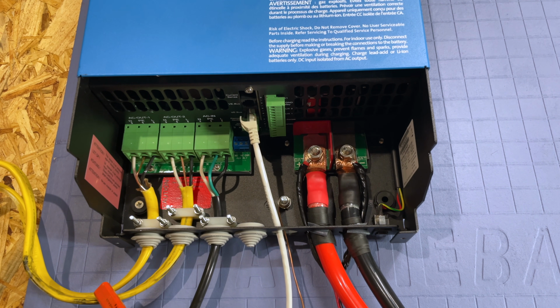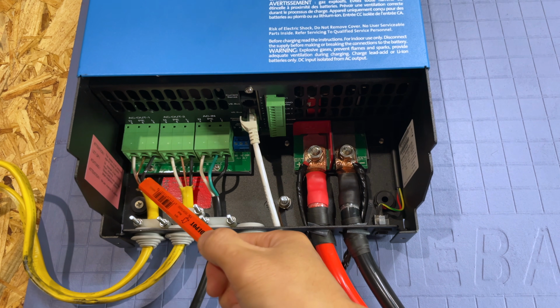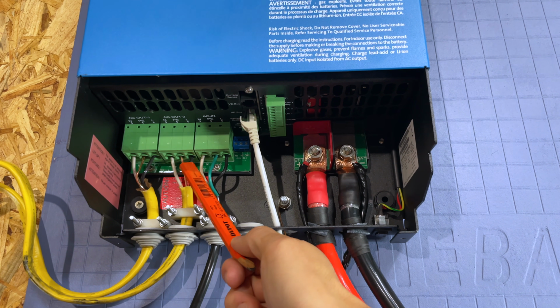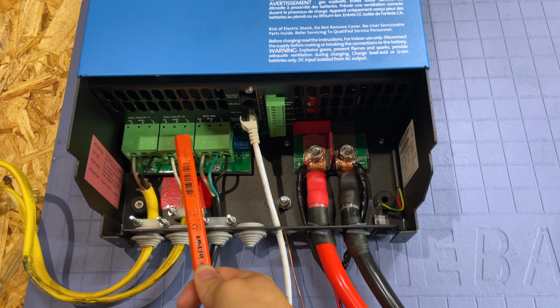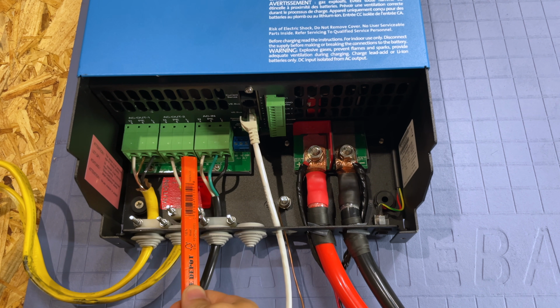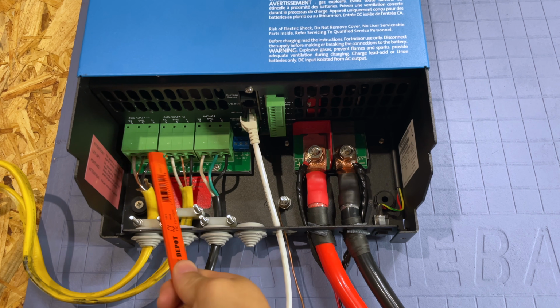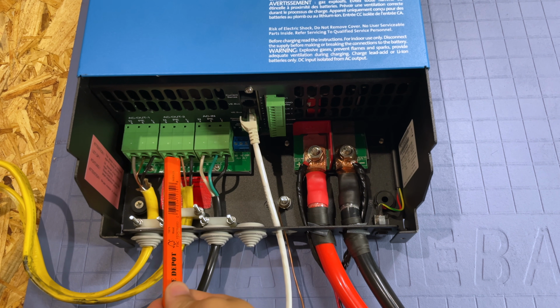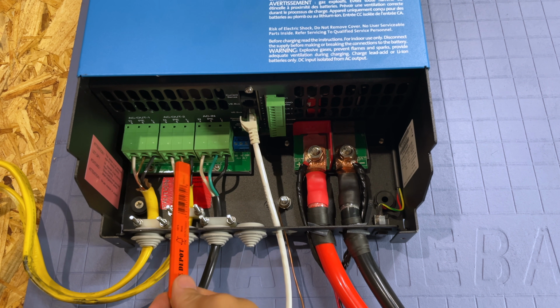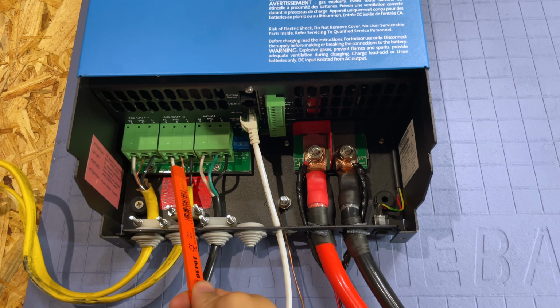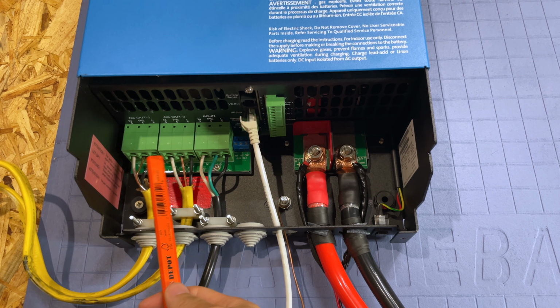I'm pretty much using here 12 gauge Romex. And the 12 gauge Romex is solid, so when you put it into these terminals here, you don't really need a ferrule. But if you're using thin stranded wire, you do need to. But if you're using something like, let's say, 6 gauge, it's stranded, but it's like thick core stranded, so you probably don't need to put a ferrule on here.